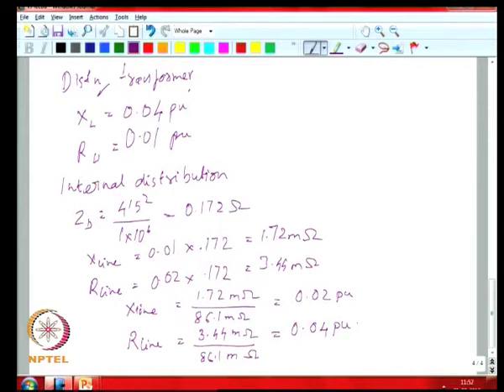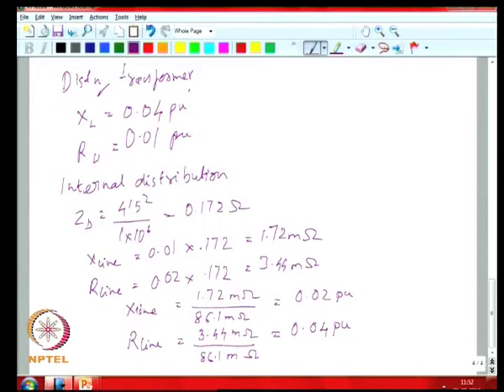Because you went from a 1 MVA base level where it was specified to a higher base, your 1 percent reactance of the line got scaled up to 2 percent because you are going up to a larger base quantity. You could either go to the physical quantity and then derive by the actual base quantities, or use the change-of-base equation mentioned in the previous class.